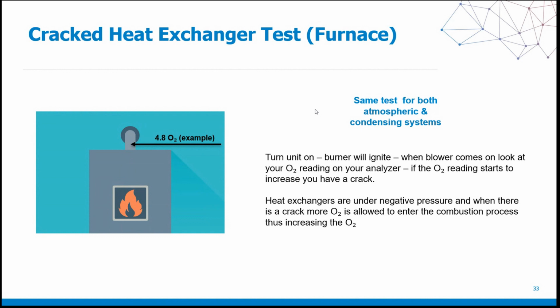With a combustion analyzer, you're able to check and test for a cracked heat exchanger in about 30 seconds. And the way that you do that is this. Whether it's an atmospheric or condensing system, it doesn't matter, as long as it's a forced air system. The system is going to be off. You insert your probe into the stack, into the exhaust. You turn the system on, and the combustion process begins. You look at your oxygen levels once they stabilize. It's going to be anywhere from 3 to 6% or 3 to 9%, depending, but mostly between 3 and 6. For our example today, we're going to say 4.8, as you see with my little highlighter here.